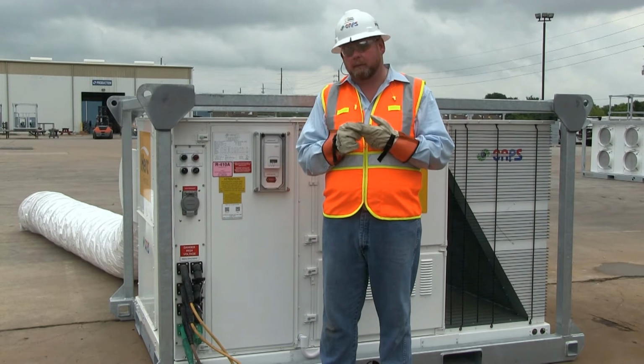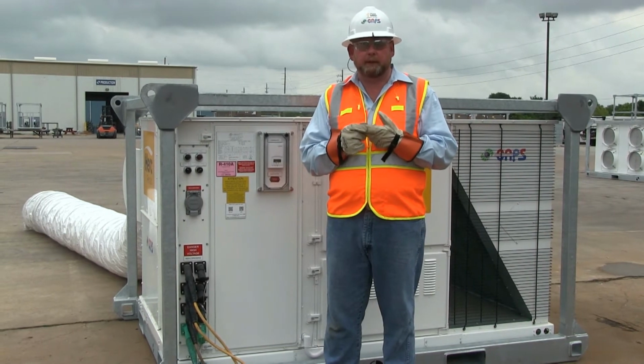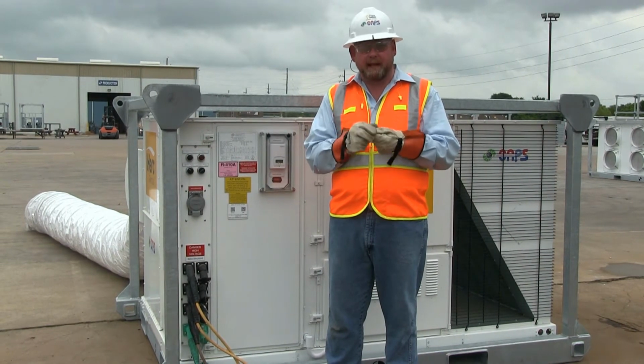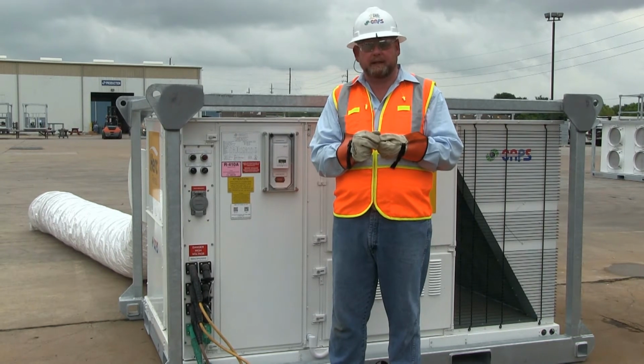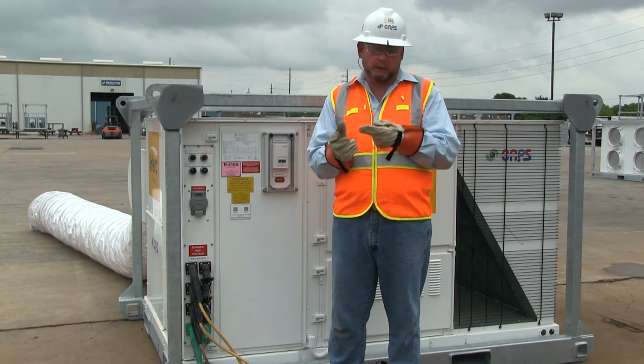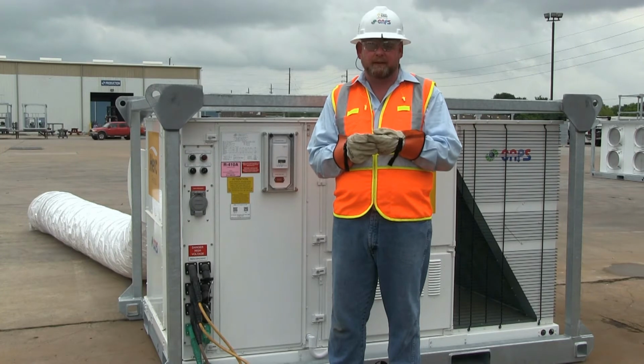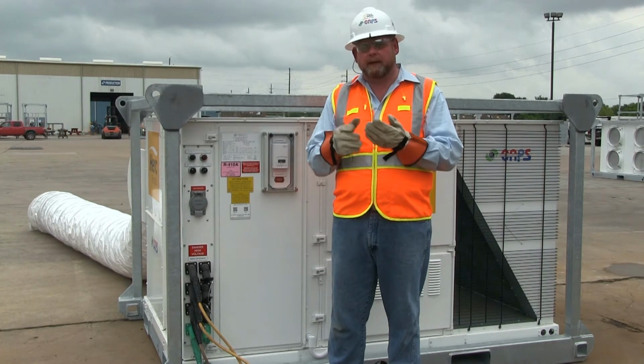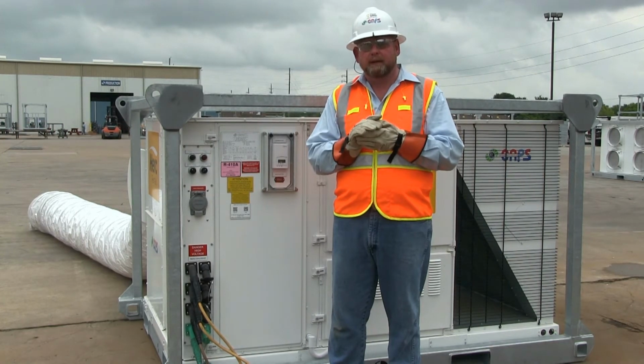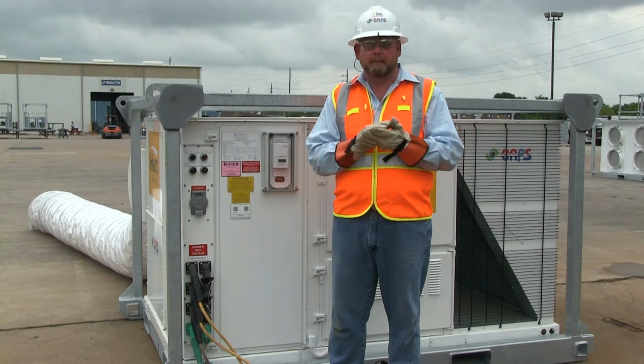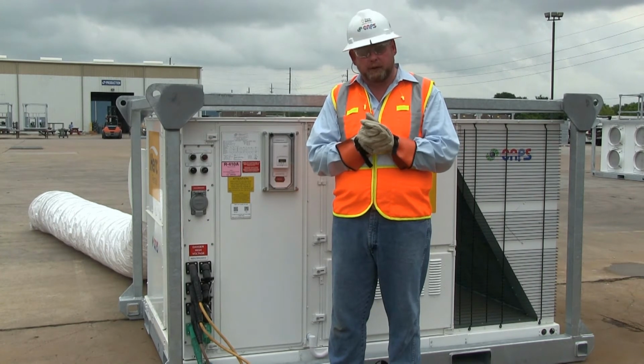We verified our power requirements for both heating, cooling, and dehumidification. We've connected our power supply to the machine and verified or corrected the phase rotation. We've connected our ductwork both in and out of the space being served, and we've primed our condensate trap. The last step now is to do the unit startup.